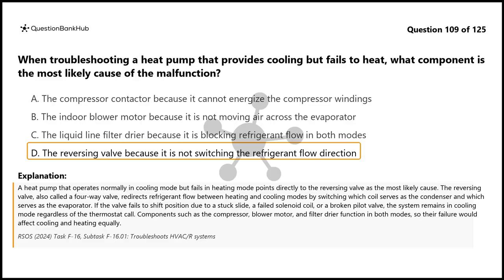If the valve fails to shift position due to a stuck slide, a failed solenoid coil, or a broken pilot valve, the system remains in cooling mode regardless of the thermostat call. Components such as the compressor, blower motor, and filter dryer function in both modes, so their failure would affect cooling and heating equally.